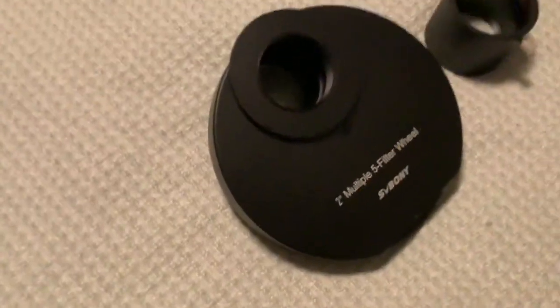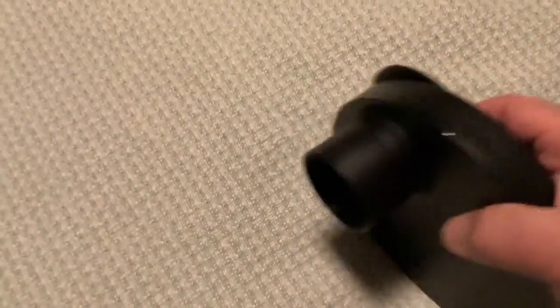I'm attempting an explanation video for the filter wheel from SVBONY. What's wrong is this plate here came installed at the wrong spot. You can see the nose piece for the 2-inch interface is on the other side.